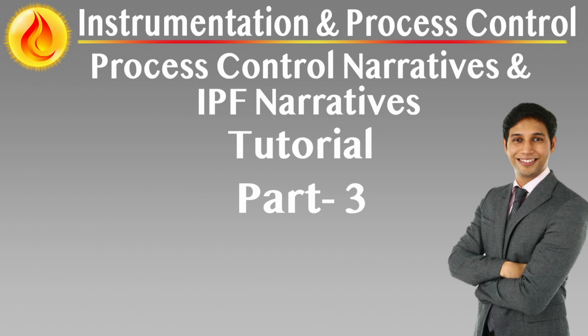Alarm narratives also serve as a foundation for alarm system configuration and as an input to the alarm management lifecycle, including settings validation, training, and compliance with industry standards, e.g. IEC 62682 or ISA 18.2.